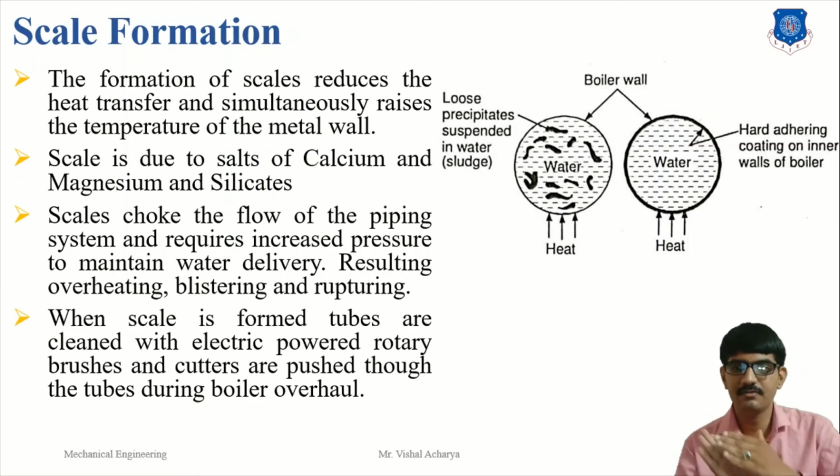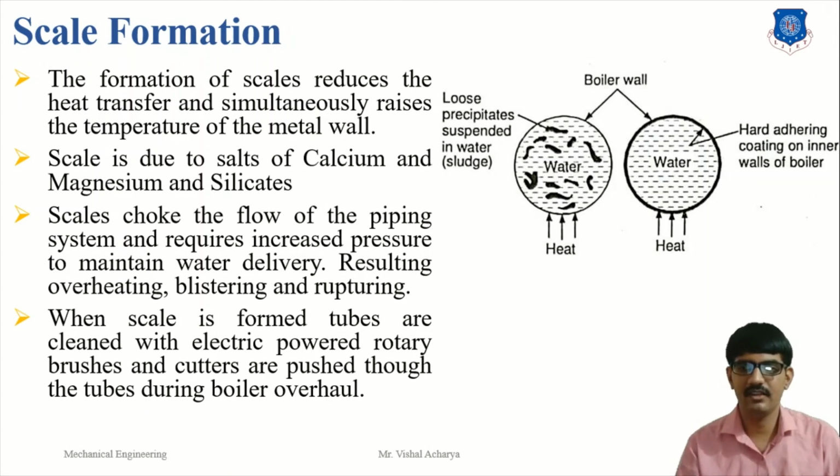When scale is formed, the tubes are cleaned with outside brushes, and cutters are pushed through the tubes during the boiler maintenance or overhaul.